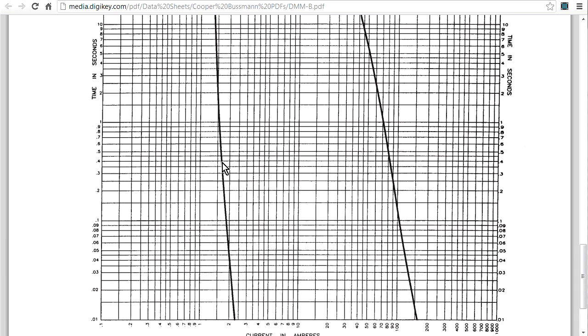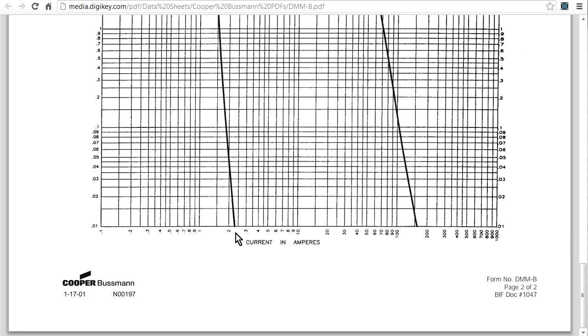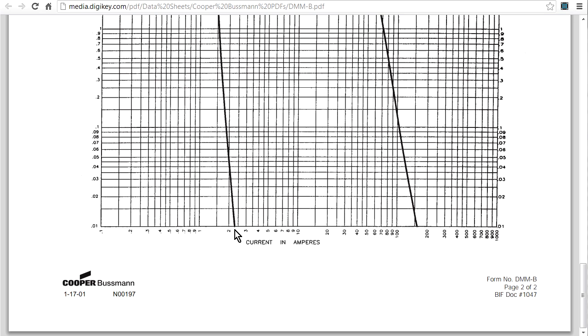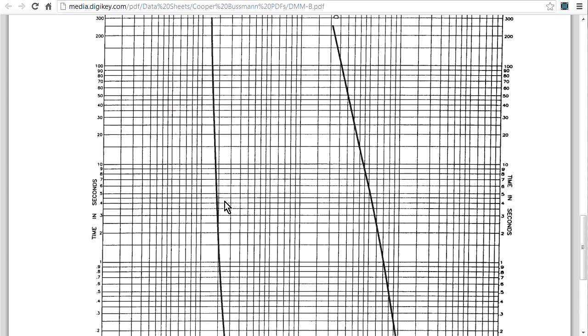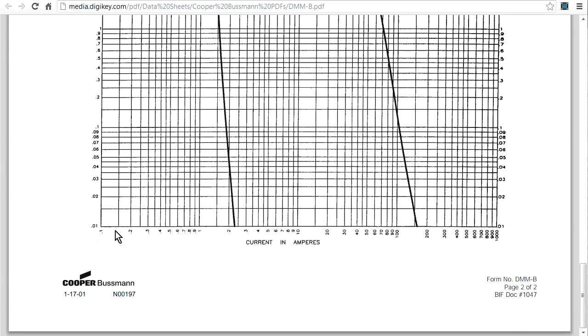Well, let's see what the lowest point on this characteristic curve is. It's down here at let's say that's 2.4 amps or something. So if you've got 2.4 amps flowing through that 440 milliamp fuse, then it's going to blow in 0.01 of a second, or 10 milliseconds. It doesn't tell you anything faster than that. But of course, you can see that the curve is slowly branching off like that. So it's just going to get quicker and quicker, so if there's 100 amps flowing through that thing, it's going to blow practically instantaneously.